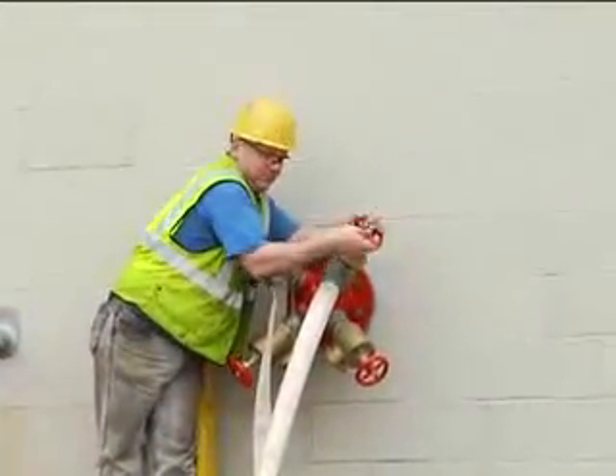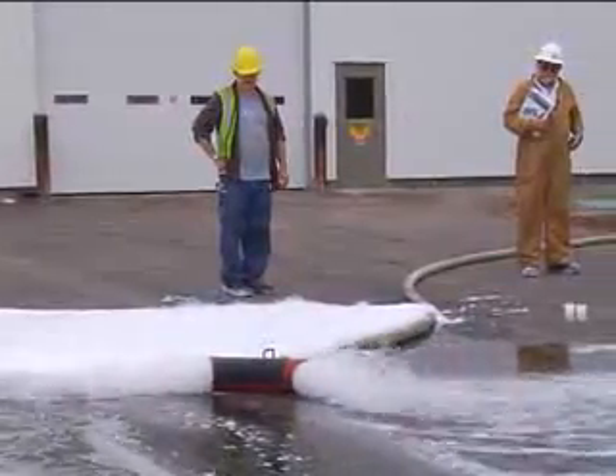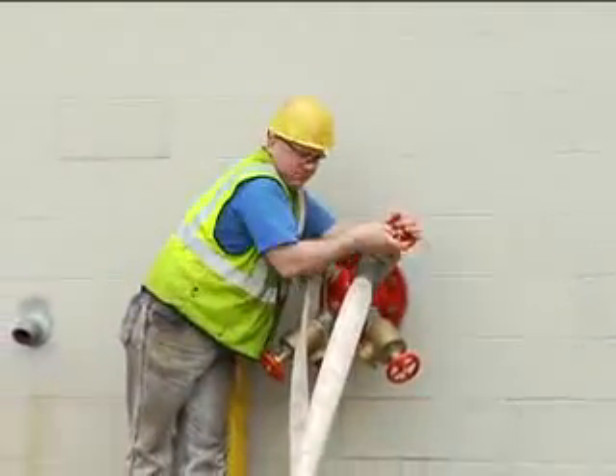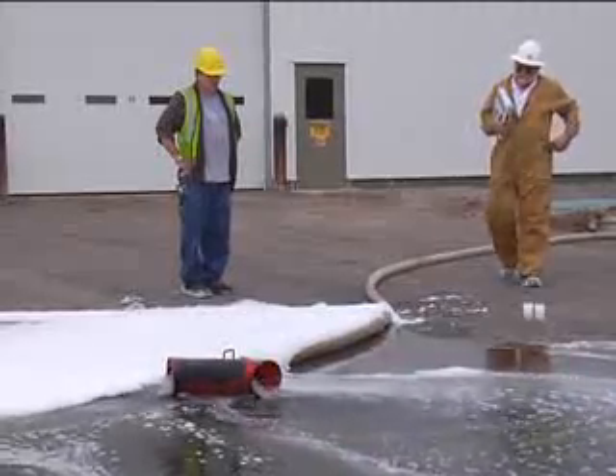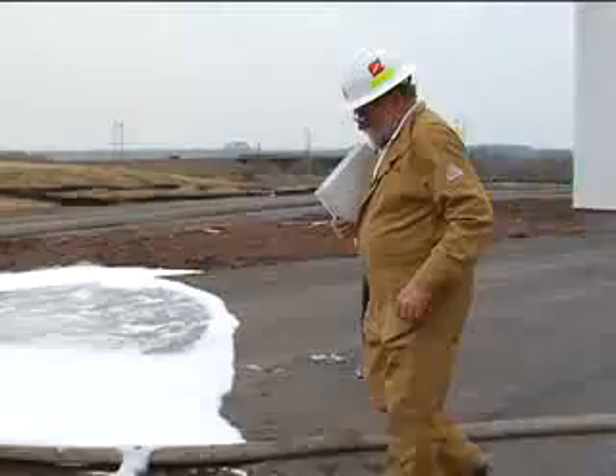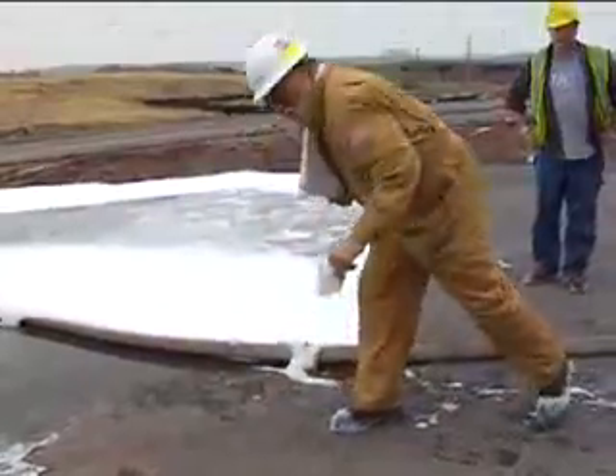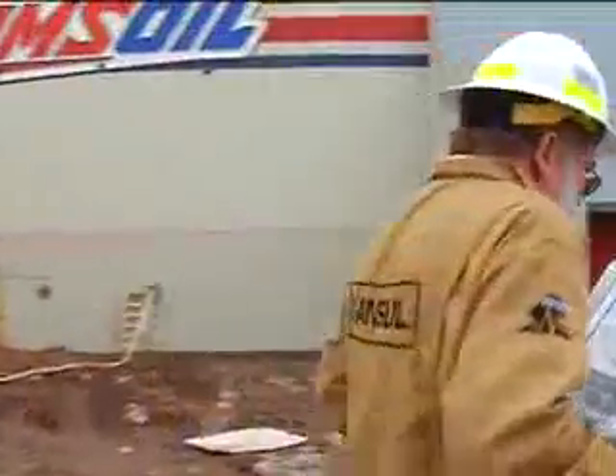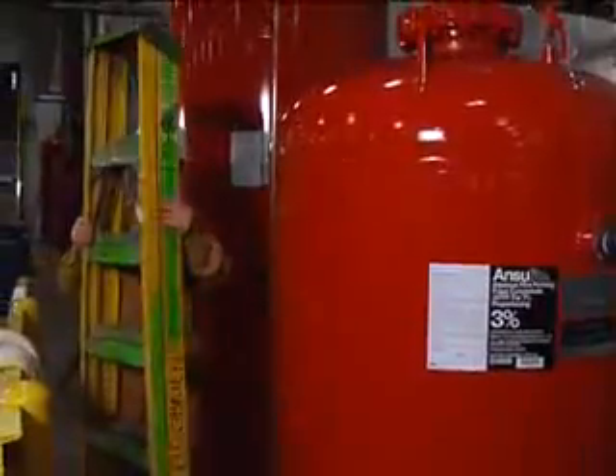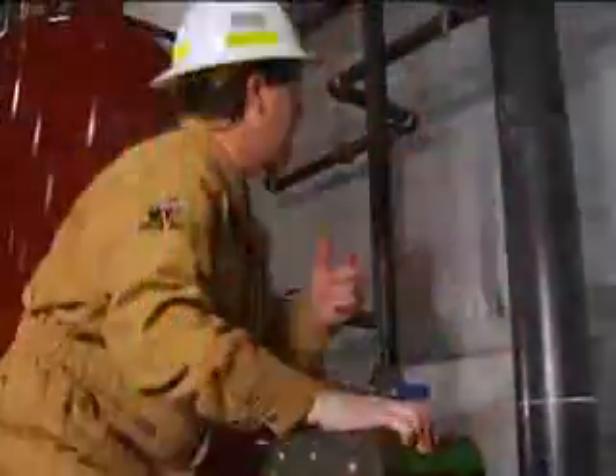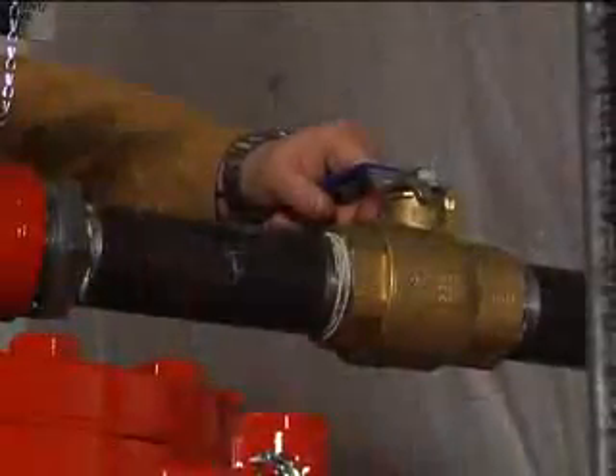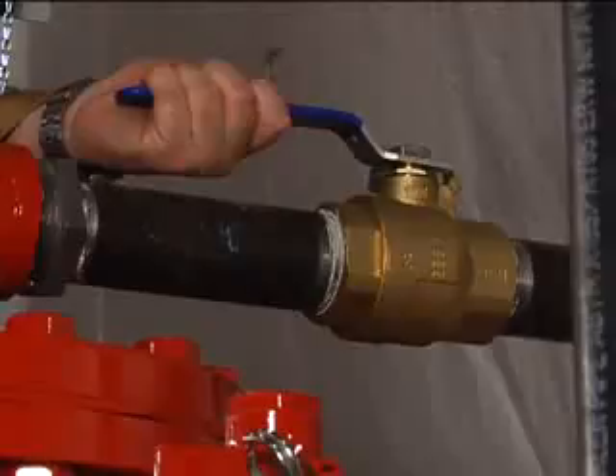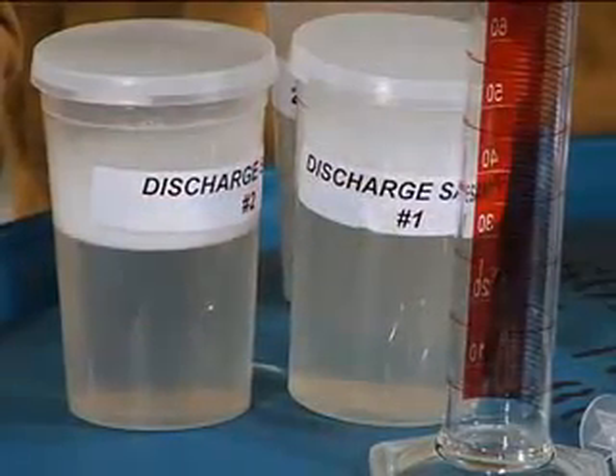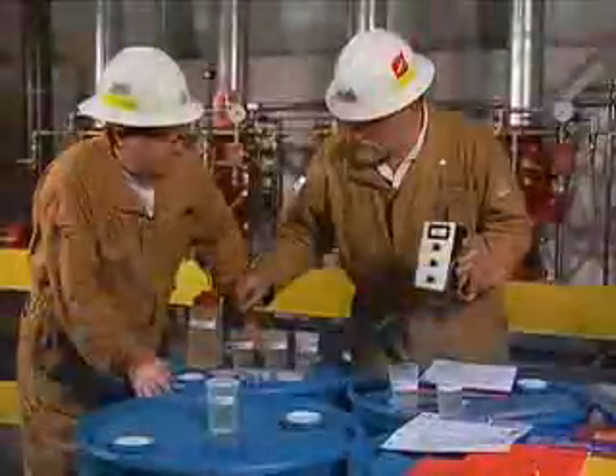Okay, it looks like we got her flushed down good. We can shut it down. All right, now we're ready to take these samples back and test them. At this point, pressure is relieved from the pressure sensing line to the hydraulic actuated concentrate valve actuator, and the valve is manually reset to its normally closed position. Then the foam concentrate isolation valve is returned to its normally open position. The foam solution samples are then ready to be tested via either the refractive index or conductivity test method.